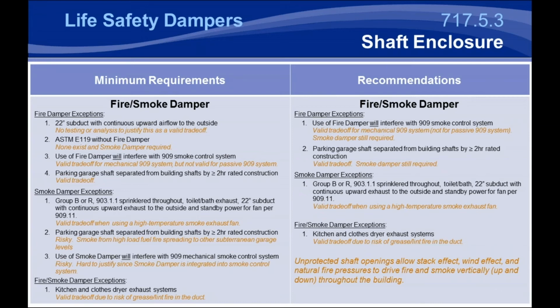One thing that we do think is a valid trade-off is removing a fire damper, say in a parking garage shaft that's separated from a building by greater than or equal to 2-hour rated construction. We think that's a valid trade-off for above ground parking structures, as you've got the required protection with that barrier. The problem is when you get into subterranean parking structures, which get risky. Once you get into subterranean parking structures, you may have occupants that have to get past a fire to exit that parking structure. And because of that, and the high fuel load that goes along with a typical parking structure, we think it's incredibly risky to eliminate the fire damper, or more importantly, the fire smoke damper from that assembly. Smoke can then spread through the parking structure and make it incredibly difficult for occupants to get out safely. And because of that, we recommend for all subterranean parking garages that you leave the fire smoke damper protection in any shaft penetrations.